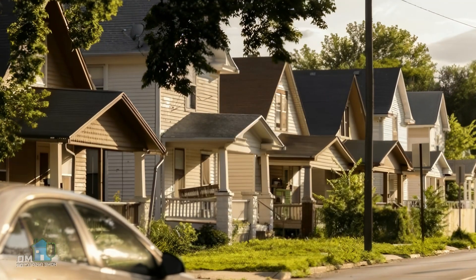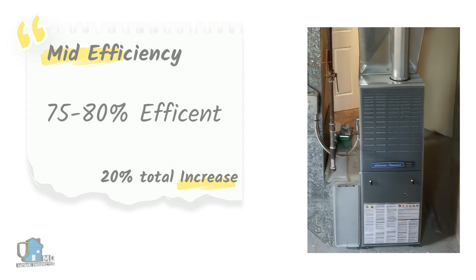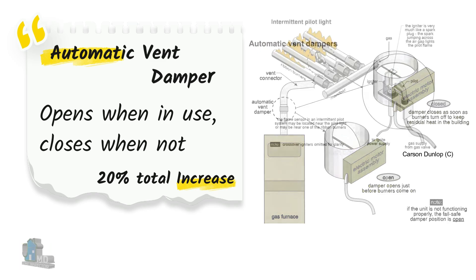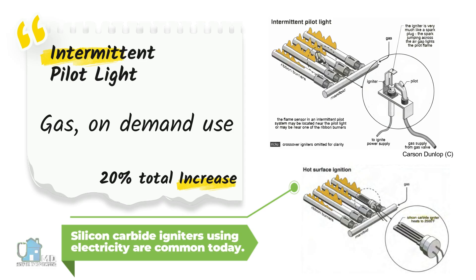There should not be any conventional furnaces operating in homes today, but there could be mid efficiency furnaces in some homes, operating past their typical life expectancy. Mid efficiency furnaces operate at about 75 to 80%. Most of that gain comes from blocking the hole in the chimney when the furnace is not in use, using an automatic vent damper — a simple metal flap that opens when the furnace is in use and closes when not. Additional savings come from replacing the continuous pilot light with an on-demand ignition.